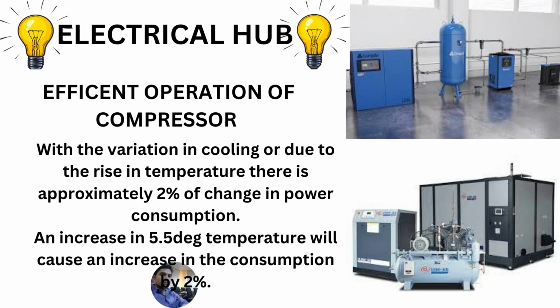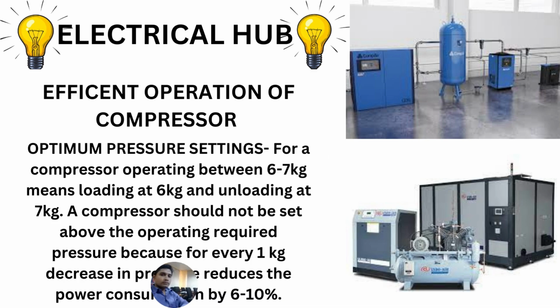So with the variation in the cooling or due to the rise in temperature, there is approximately 2% change in the power consumption. Every 5.5 degrees centigrade temperature rise will cause an increase in the consumption by 2%.